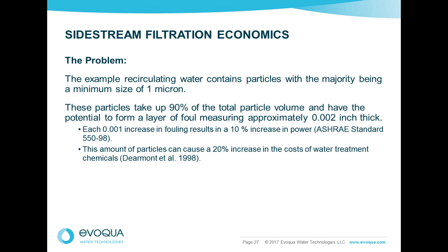So what's the problem here? In this system, the issue determined from a particle size analysis, which we'll talk about in a second, is that the particles in the water are down to 1 micron in size. And Bob said those small particles tend to stick first, and they're usually the big issue. And those particles are building up and creating a deposit 0.002 of an inch thick on the chiller tubes.